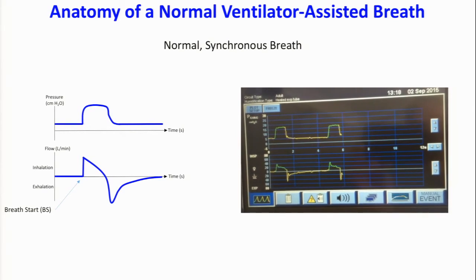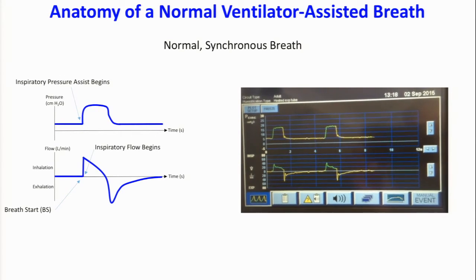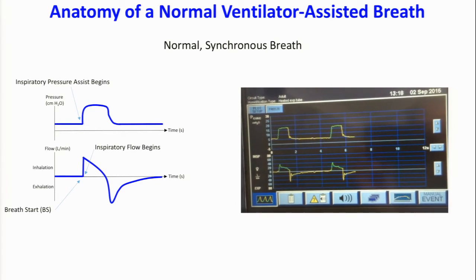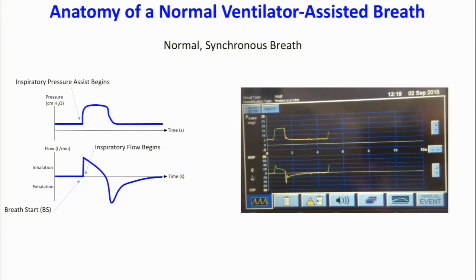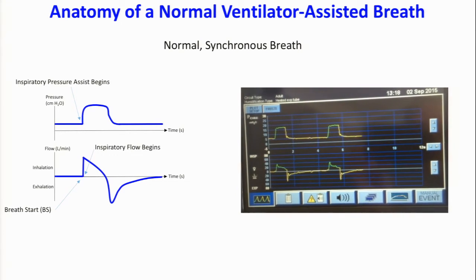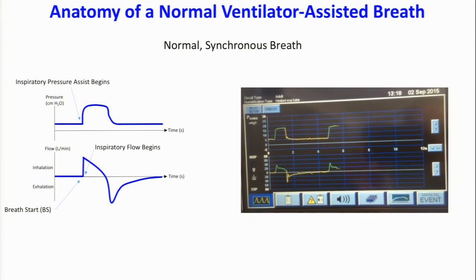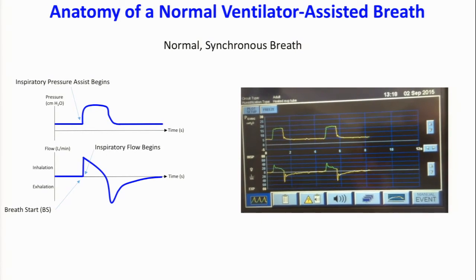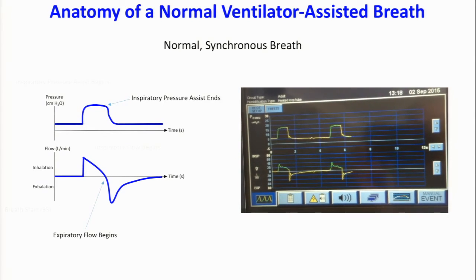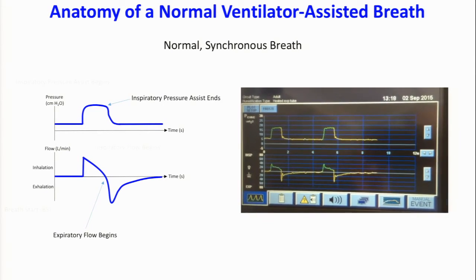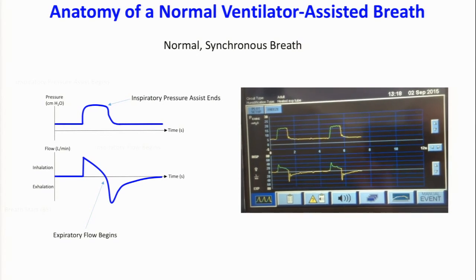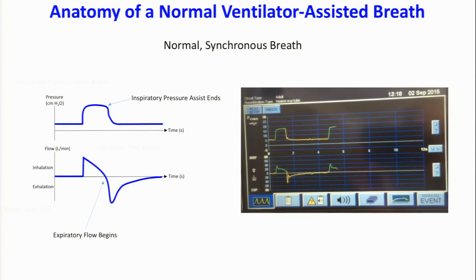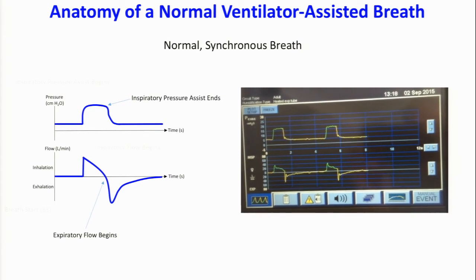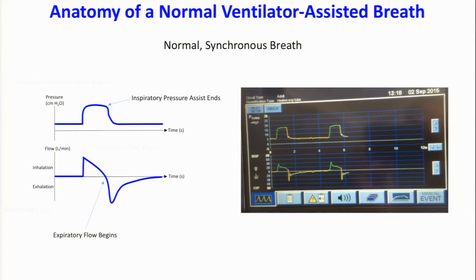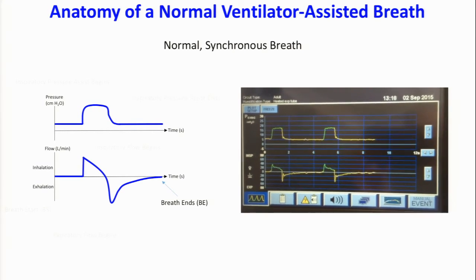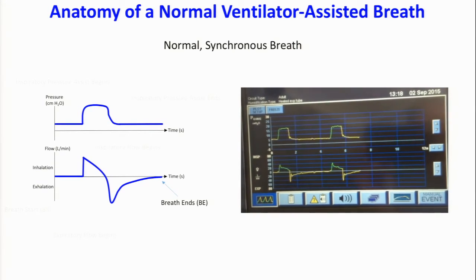So you can see down in the lower left, the breath starts, and what you see is a rapid rise in inspiratory pressure as the ventilator provides work and assistance to the patient, and flow rapidly spikes up as inspiratory flow begins. And then as the chest wall forces begin to oppose that inspiratory pressure, flow tends to slow down. And at some point, usually pre-specified by the ventilator, the assist turns off and the expiratory valve opens up, allowing exhalation to begin, which you can see down in the lower figure as the area of the curve below the zero line. And then at some point, one exhalation ends, the breath ends, and the process begins anew.